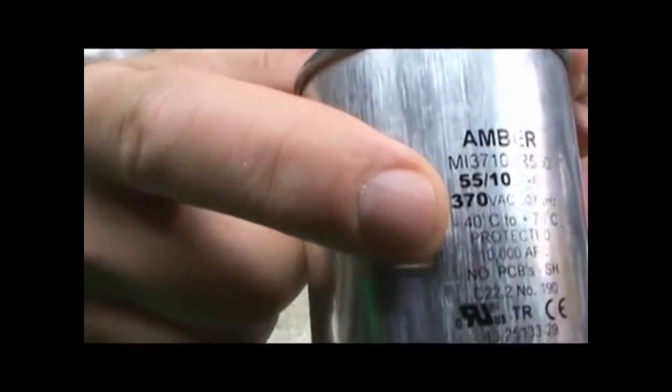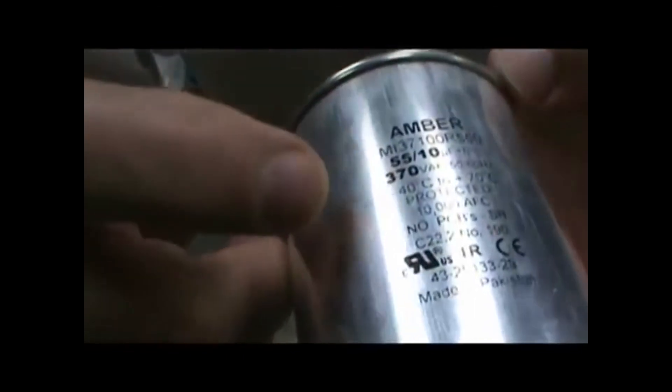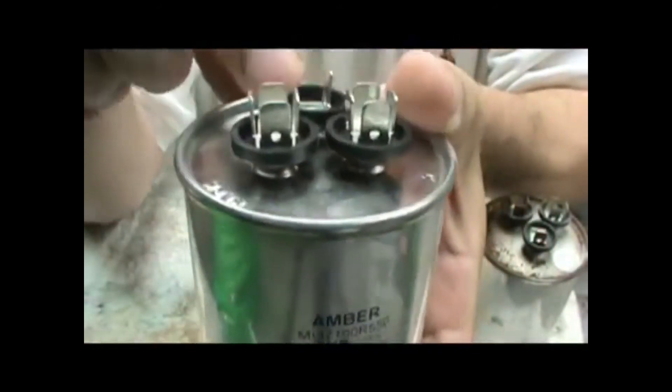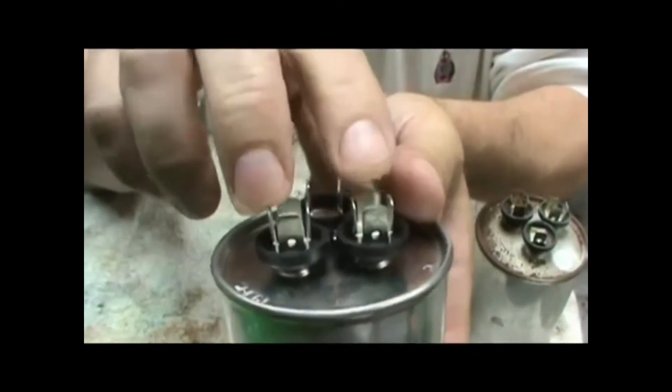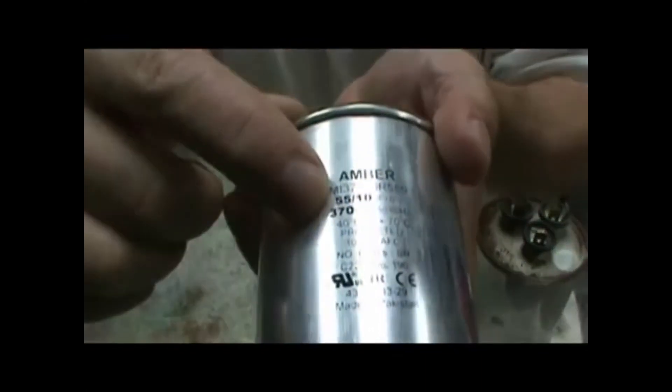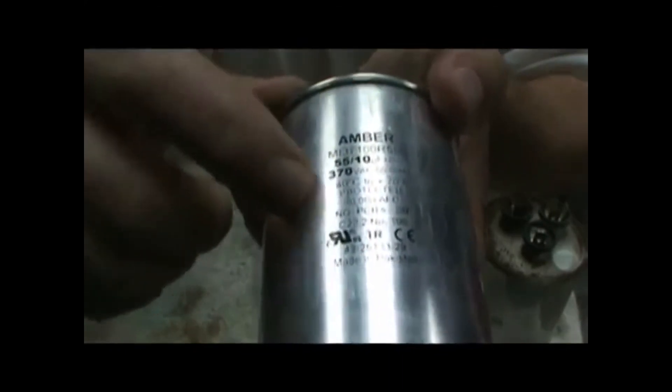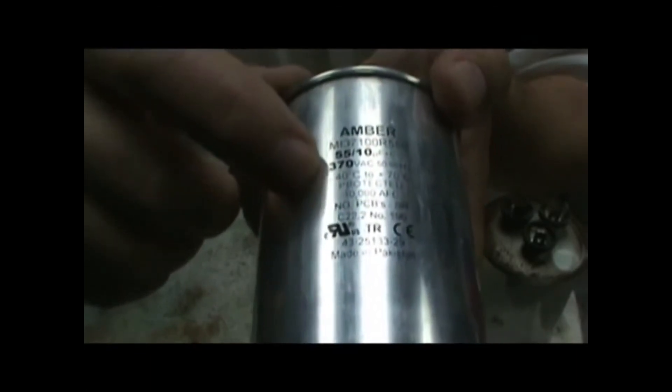Also, you need to know the voltage. In this case, it's 370. And this one is 55 and 10. So 55 and 10. When there's two numbers, it's a dual. When there's one number, it's just a single, and it just has two connections. So the 55 is going to be for the compressor, and the 10 is going to be for the fan. So you want to watch that voltage. Could be 440 or 370—those are your two choices.